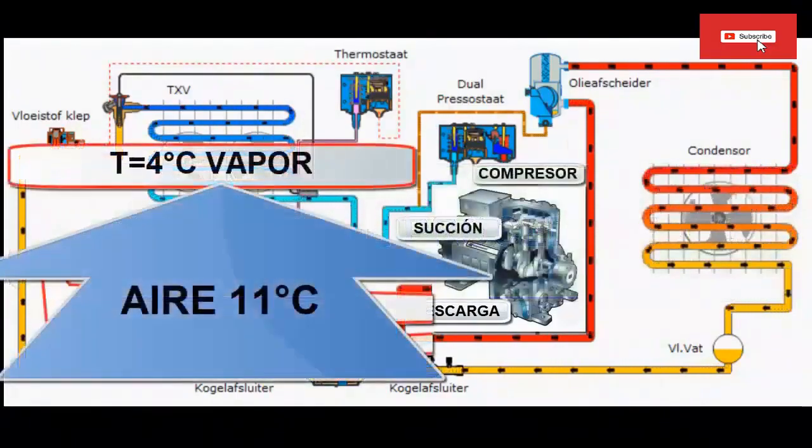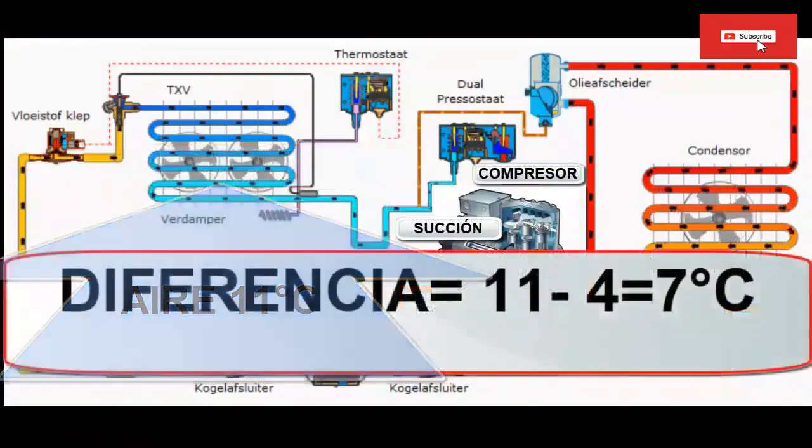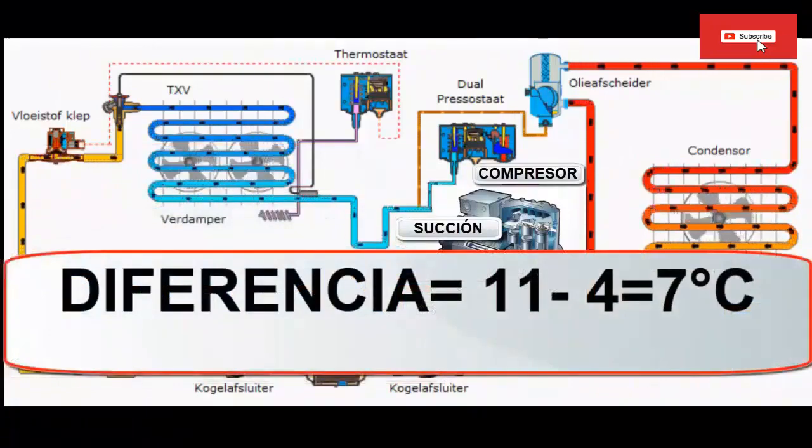In this case, the difference is calculated between the saturated refrigerant R422d at 4 degrees C and the cold room air at 11 degrees C, for a difference of 7 degrees C. Let's go with Step 2.